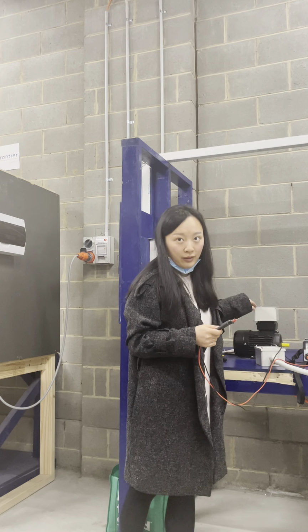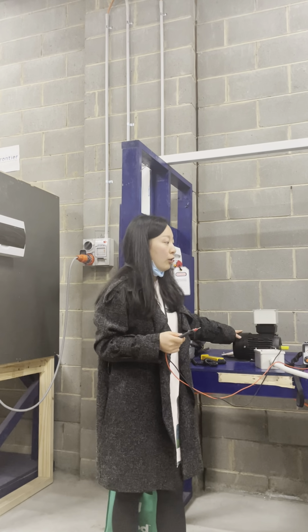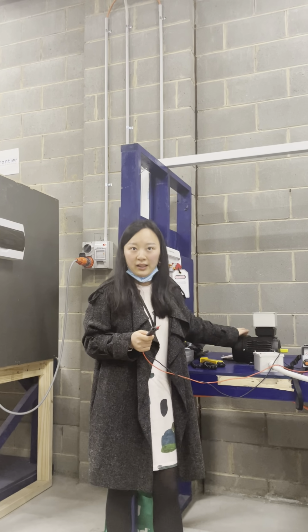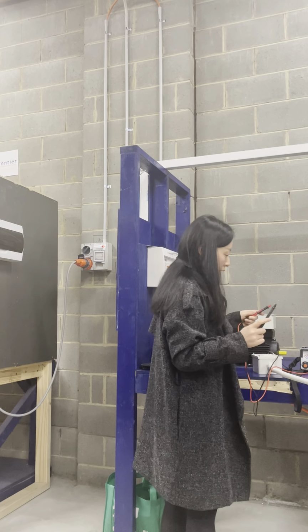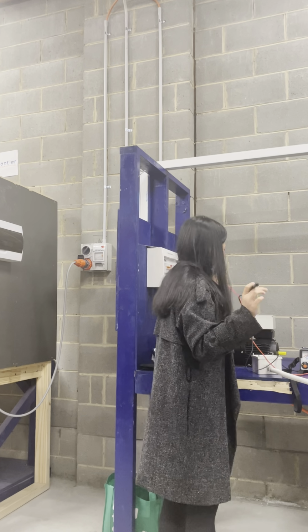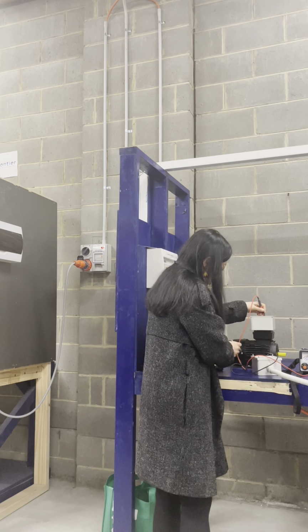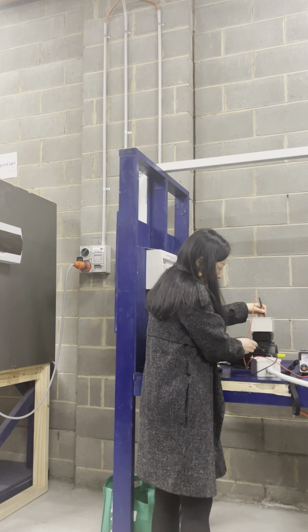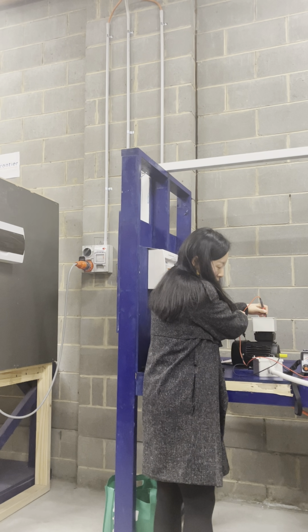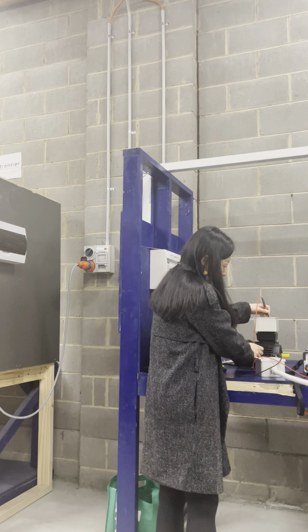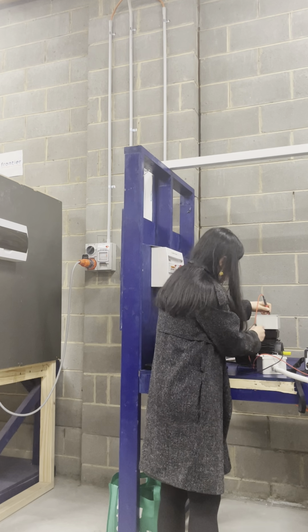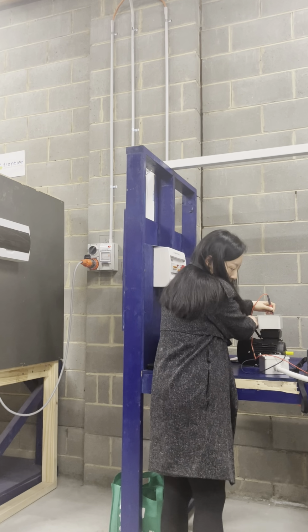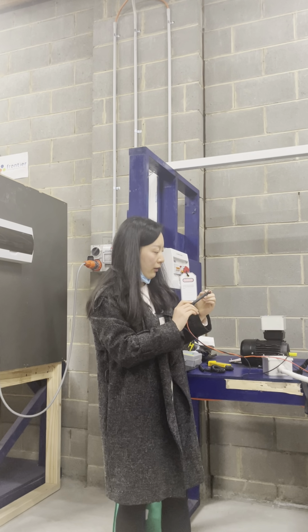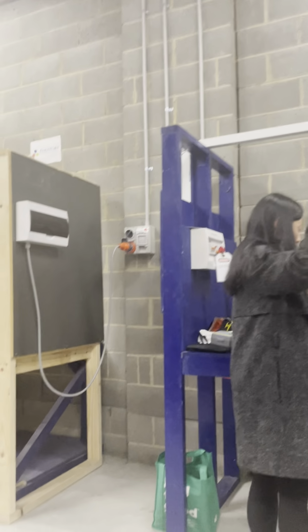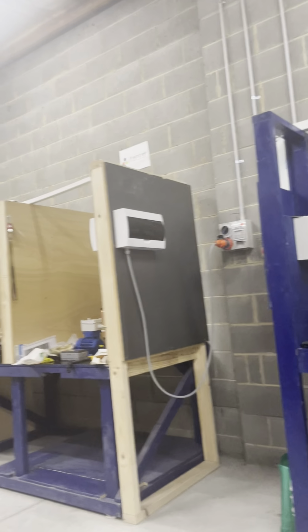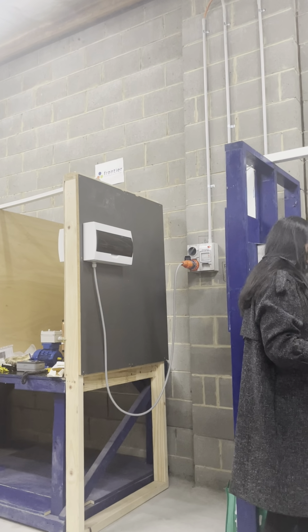Now we need to check the earth continuity on this appliance itself. You don't need to check between here and here because nothing is terminated yet. So now I'm checking earth continuity. Test your tester. 0 ohms between earth and the 3 points, 0.1, 0, 0.2, 0.1, something like that, 0.3. Yeah, 0 ohms, that's good. We test your tester. Okay, that's good. So far we've confirmed this appliance passed both of the 2 tests.